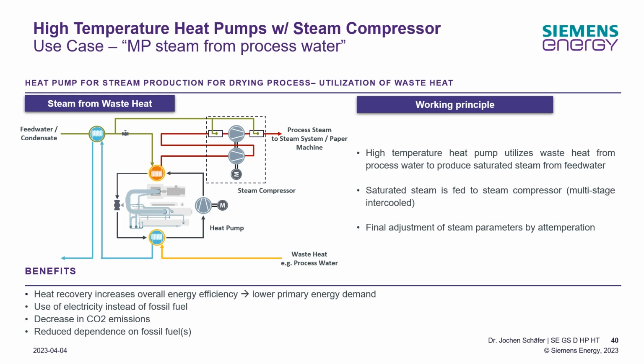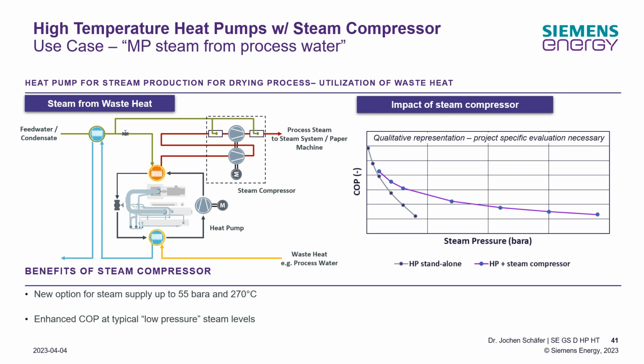There's a technical aspect I'd like to emphasize: there is a certain range of pressure levels we can achieve using the high temperature heat pump only, as sketched here. Here is the pressure level and here's the coefficient of performance. If we go higher, we see a rather steep decrease of the coefficient of performance with pressure level, and there is a certain overlap ratio, as I mentioned.